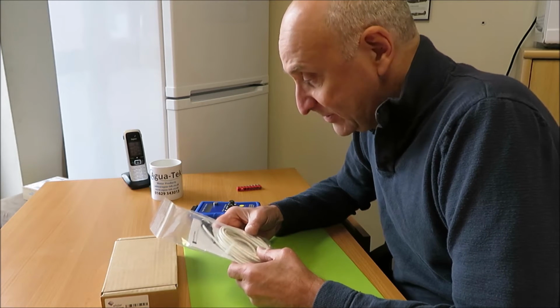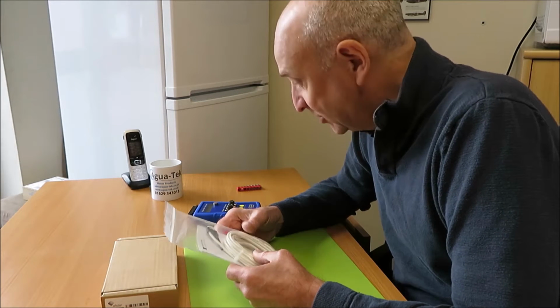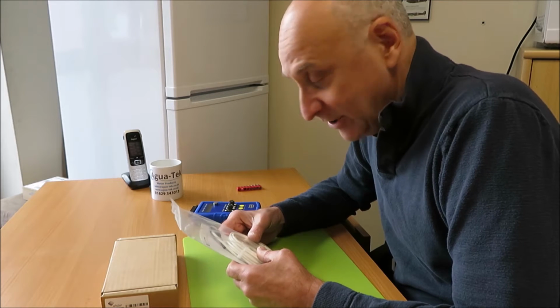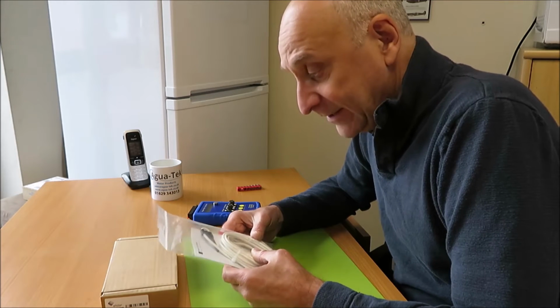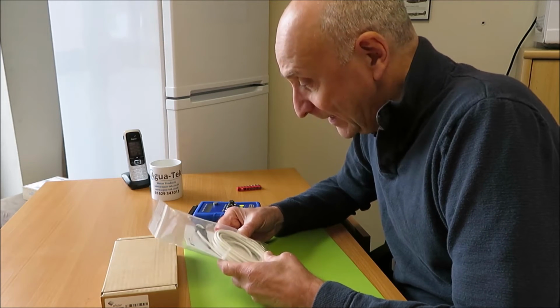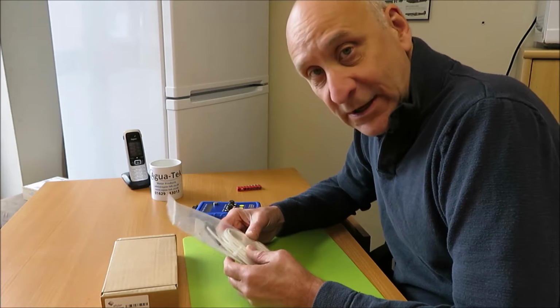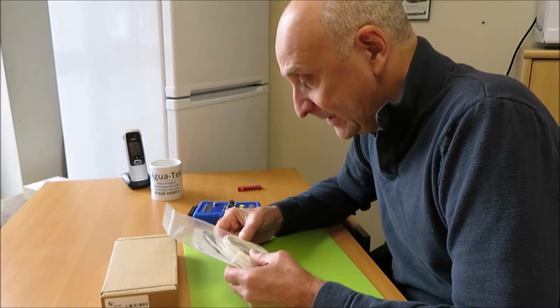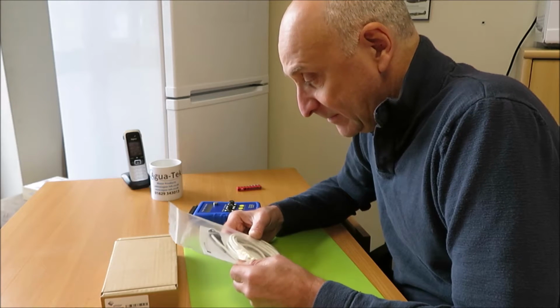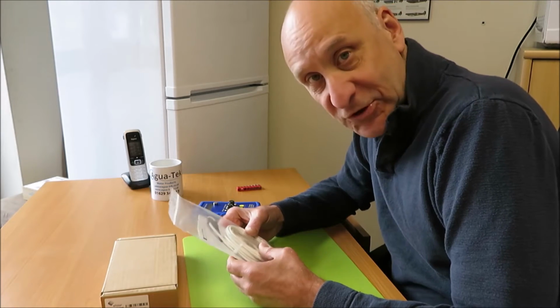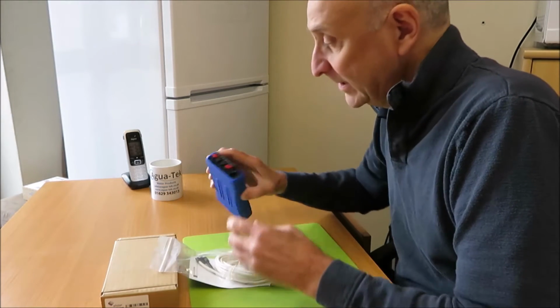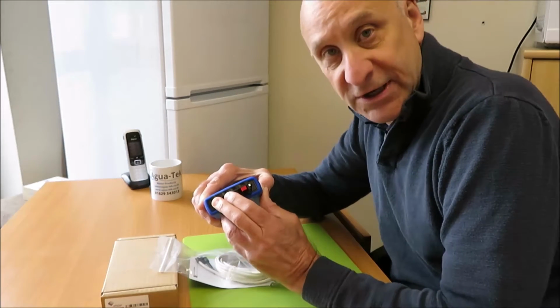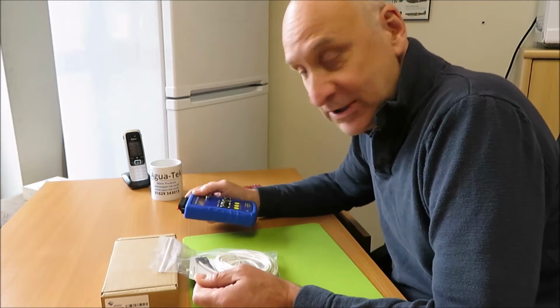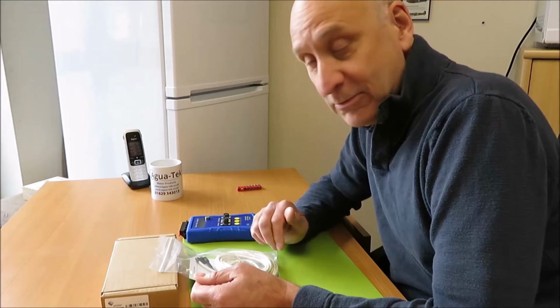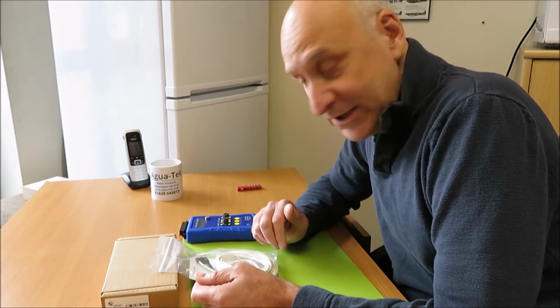I realised that that's a good opportunity for me to demonstrate the pulse test unit, checking the flow sensor prior to me actually terminating them with a connector. I also thought it was a good opportunity to show you the bare wire operation of the pulse test unit, using these two sockets, and how to test the flow sensor to ensure that it's operating correctly.